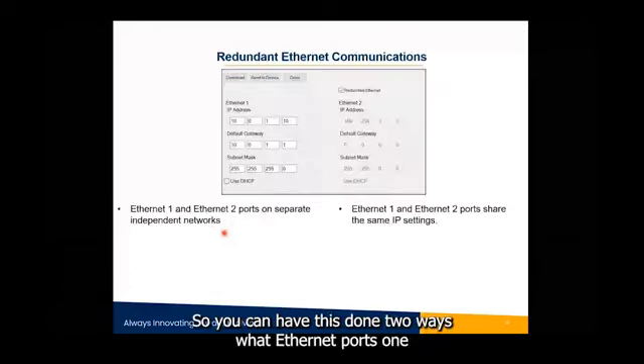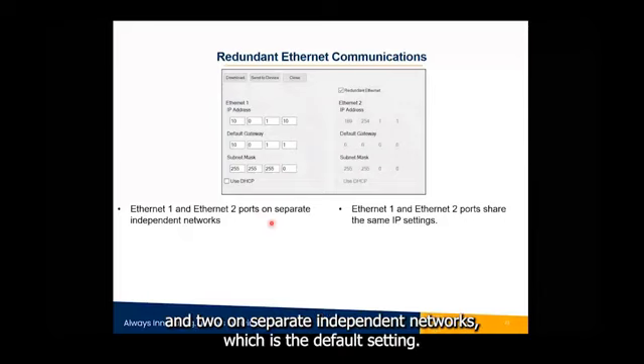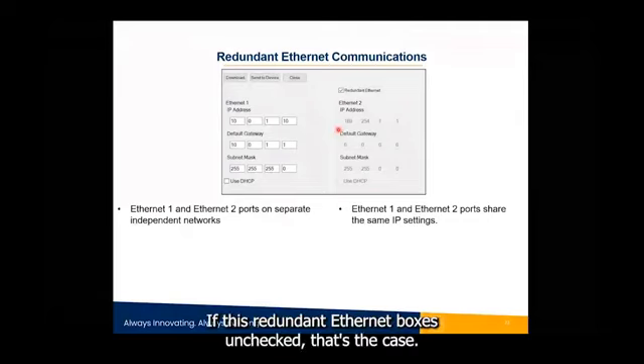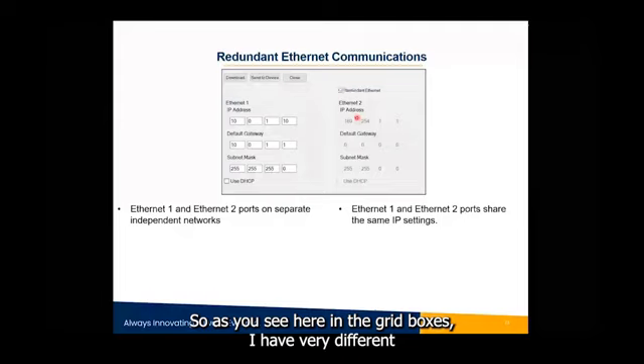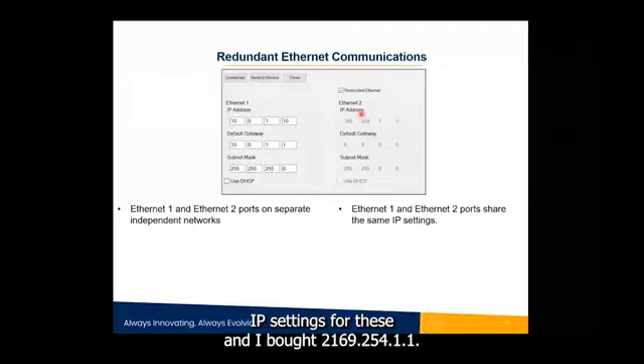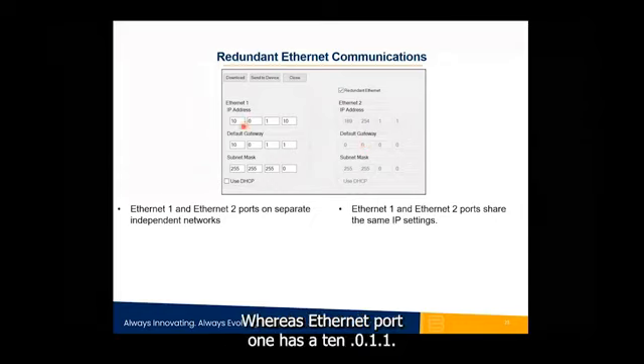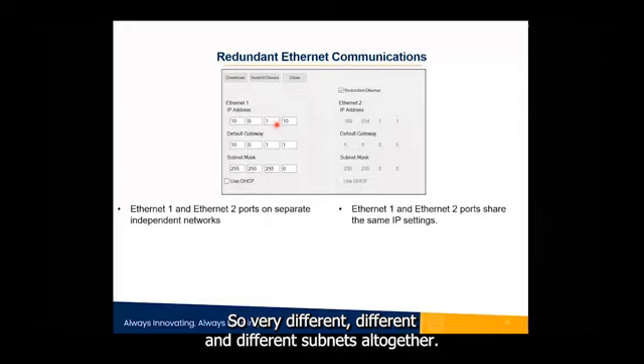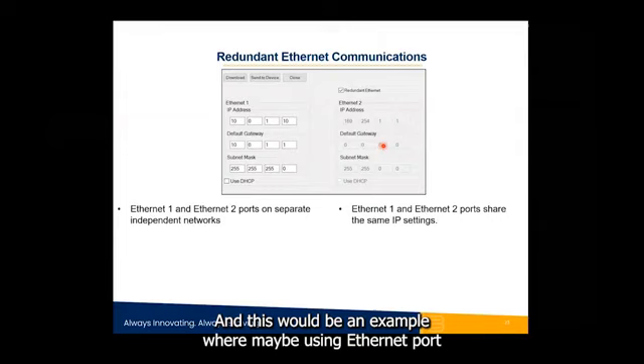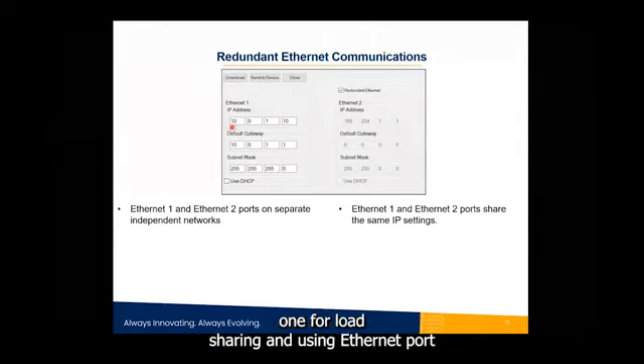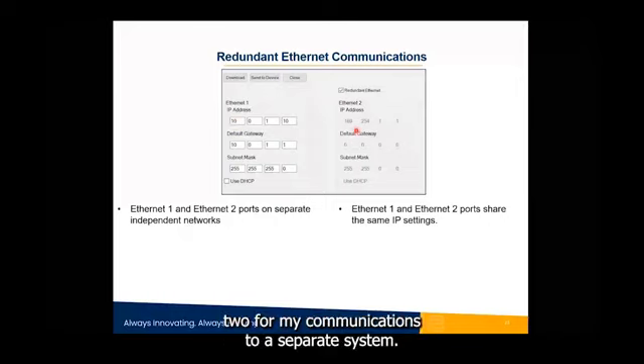in the event that it fails. You can have this done 2 ways. Ethernet ports 1 and 2 can be on separate independent networks, which is the default setting, if this redundant Ethernet box is unchecked. As you see here in the grayed out boxes, I have very different IP settings for Ethernet port 2, 169.254.1.1, whereas Ethernet port 1 has 10.0.1.10. So very different, they're on different subnets altogether. This would be an example where maybe you're using Ethernet port 1 for load sharing and Ethernet port 2 for Modbus communications to a separate system.